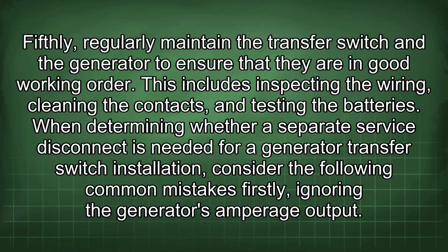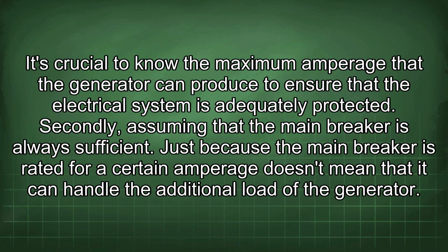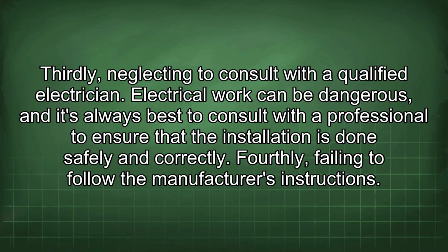Firstly, ignoring the generator's amperage output. It's crucial to know the maximum amperage that the generator can produce to ensure that the electrical system is adequately protected. Secondly, assuming that the main breaker is always sufficient. Just because the main breaker is rated for a certain amperage doesn't mean that it can handle the additional load of the generator. Thirdly, neglecting to consult with a qualified electrician.